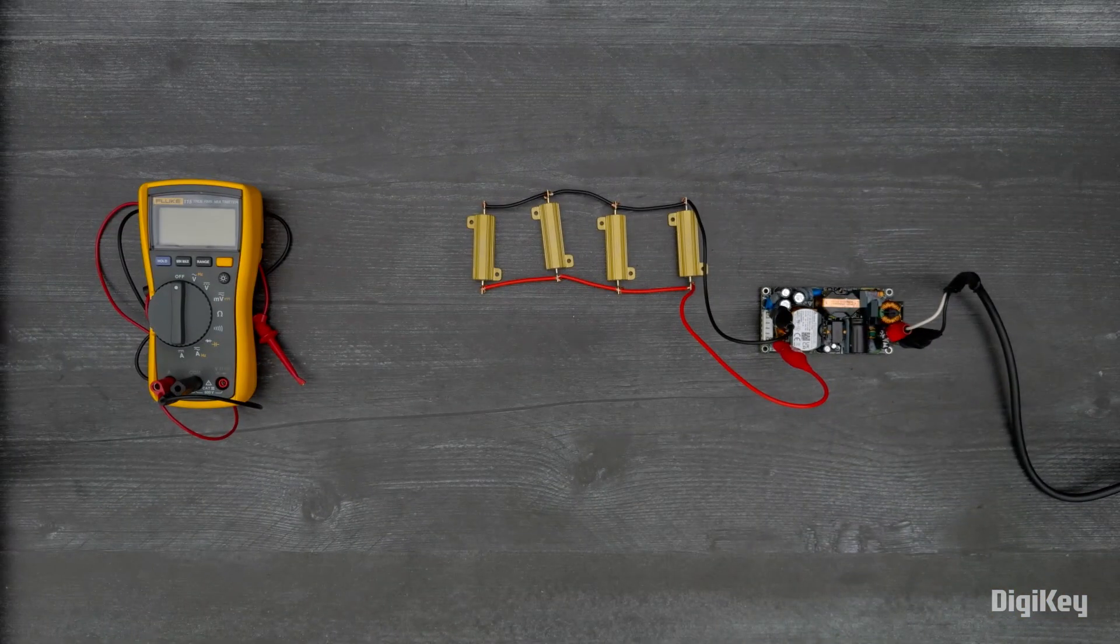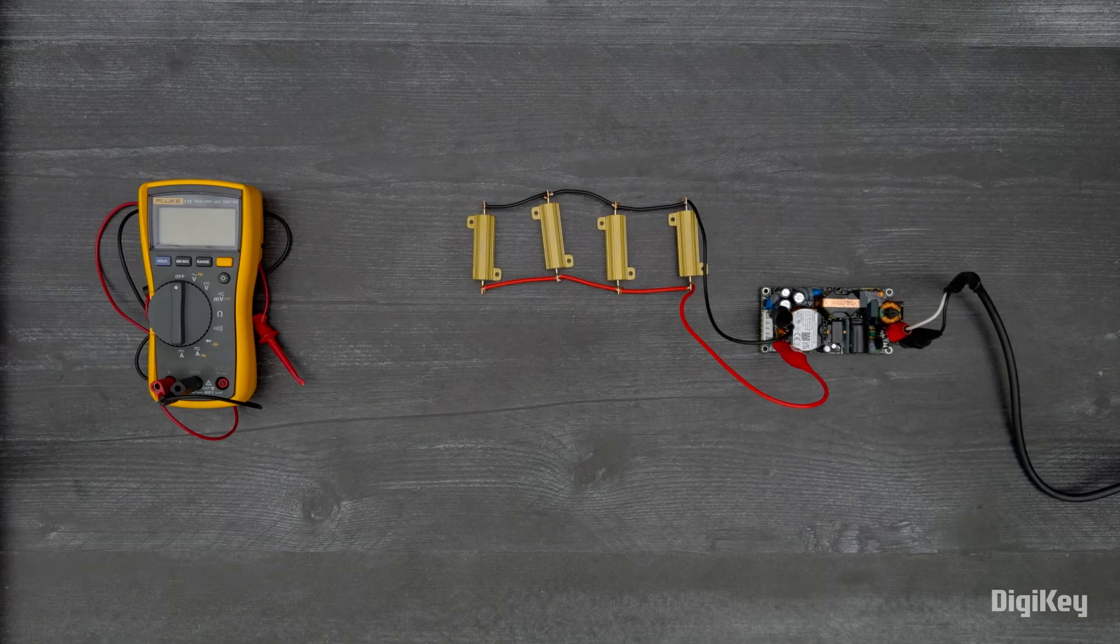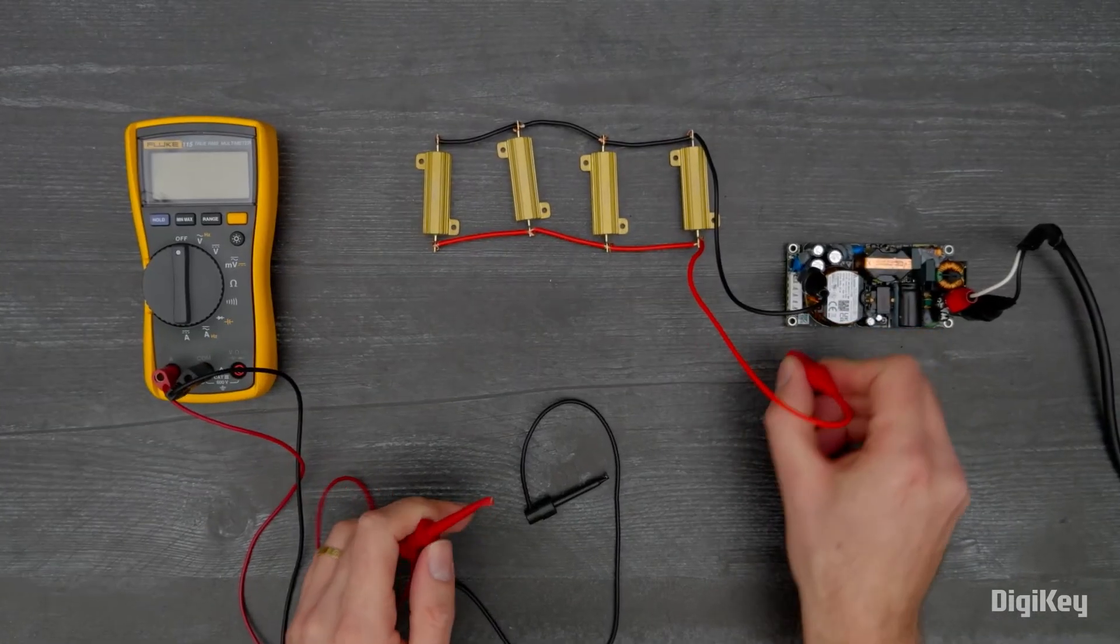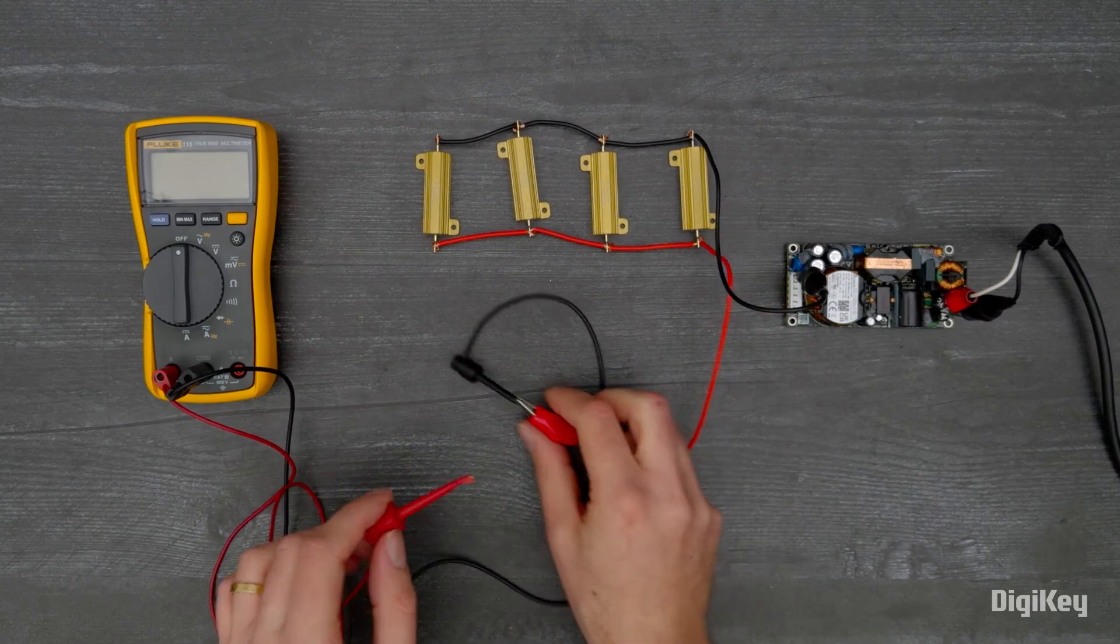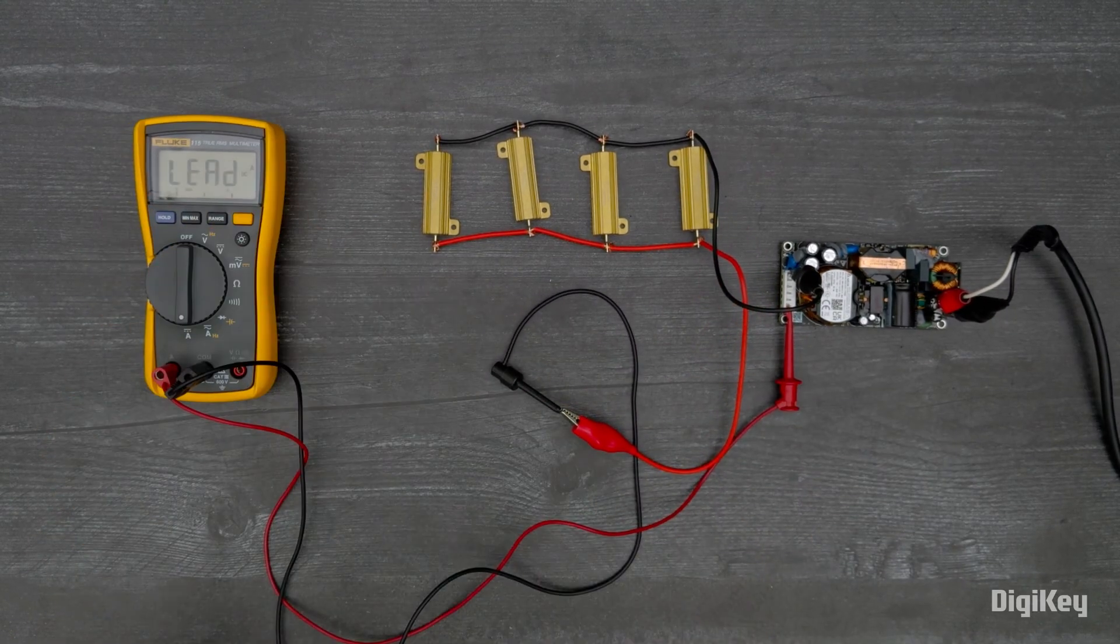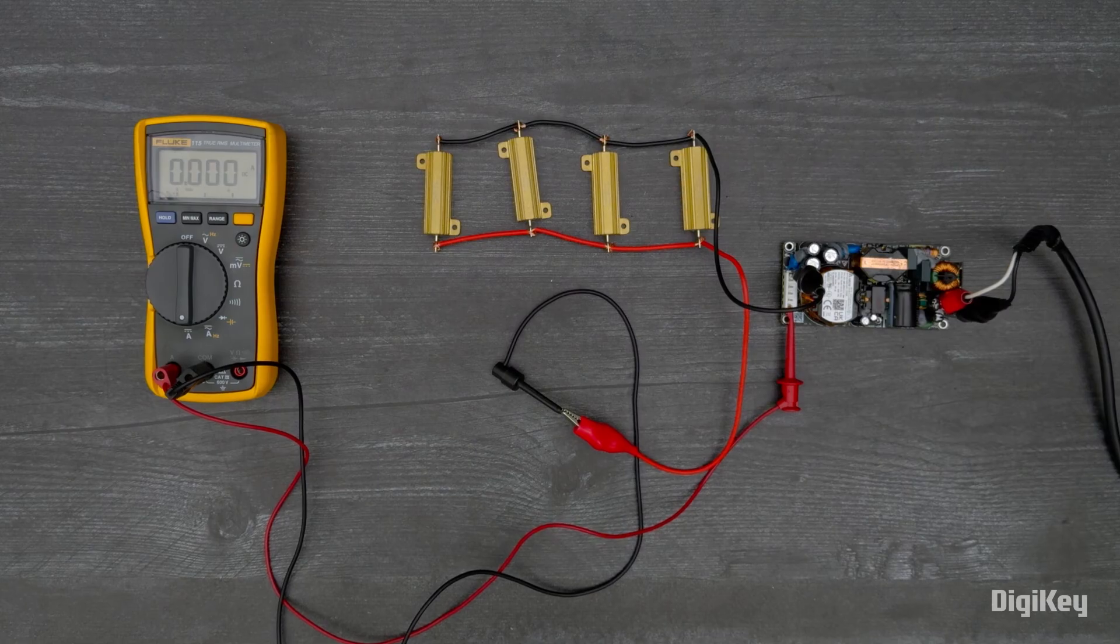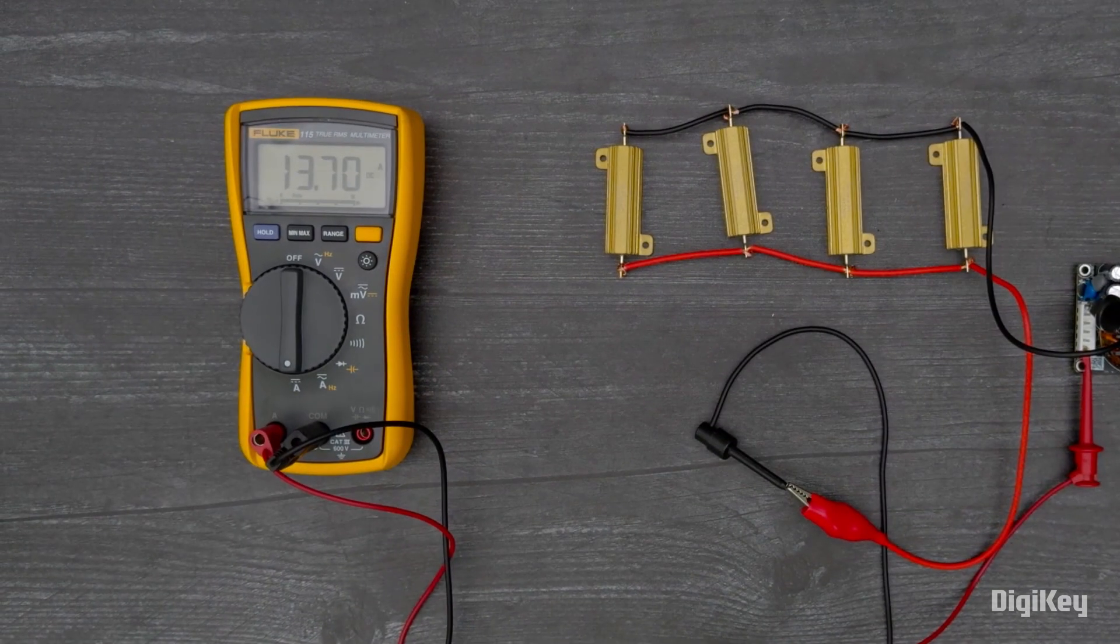To measure the output current, disconnect the input, then disconnect the pin four connection on the output connector. Now connect a DC ammeter in series. Finally, reconnect the input and measure the output at your ammeter.